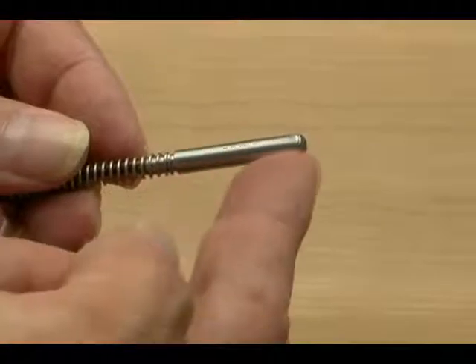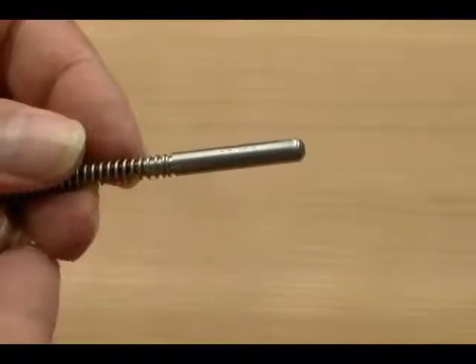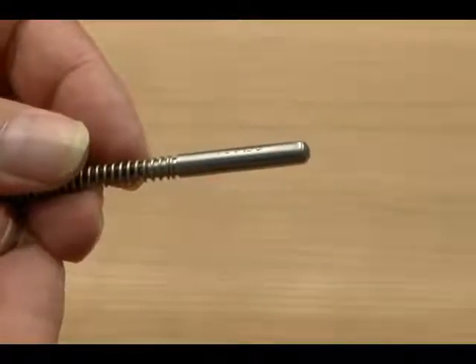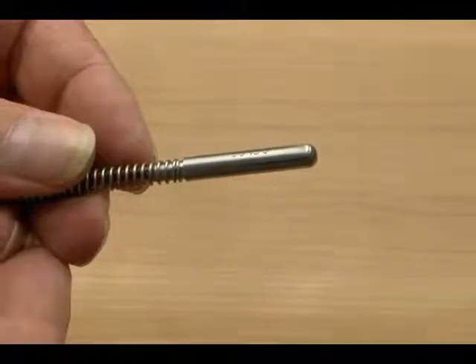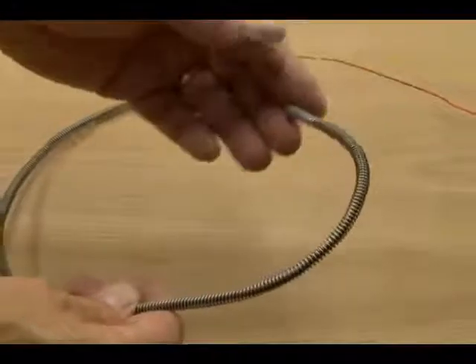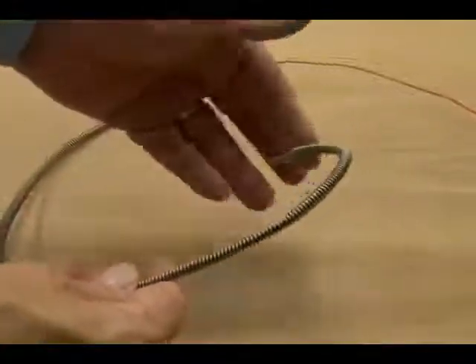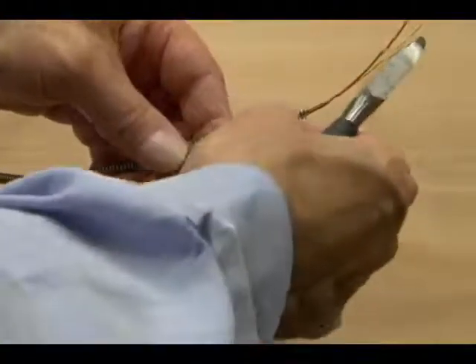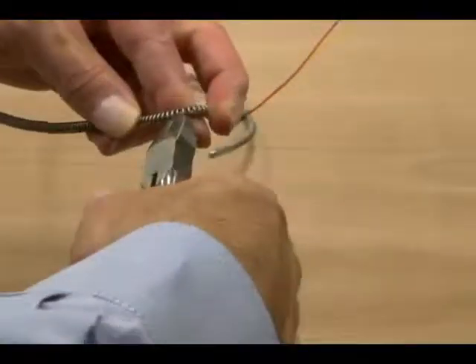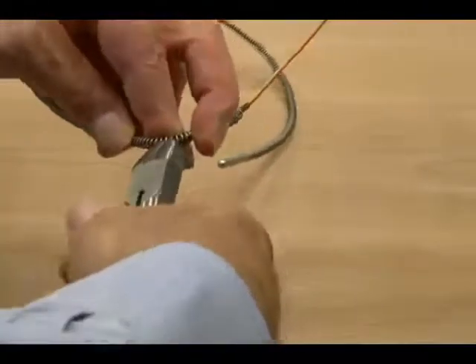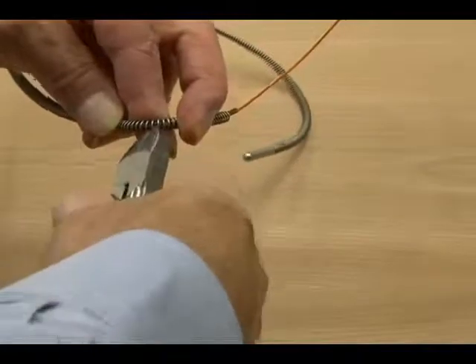The basic worm probe includes a rigid tip, but the rest of the sensor is a flexible stainless steel spring. This serves three important functions. First, it protects the wiring, but it can still bend for easy insertion. Second, it can be cut to the ideal length for a given thermal well, allowing the spring to keep the probe tip pressed into the very end of the thermal well bore.